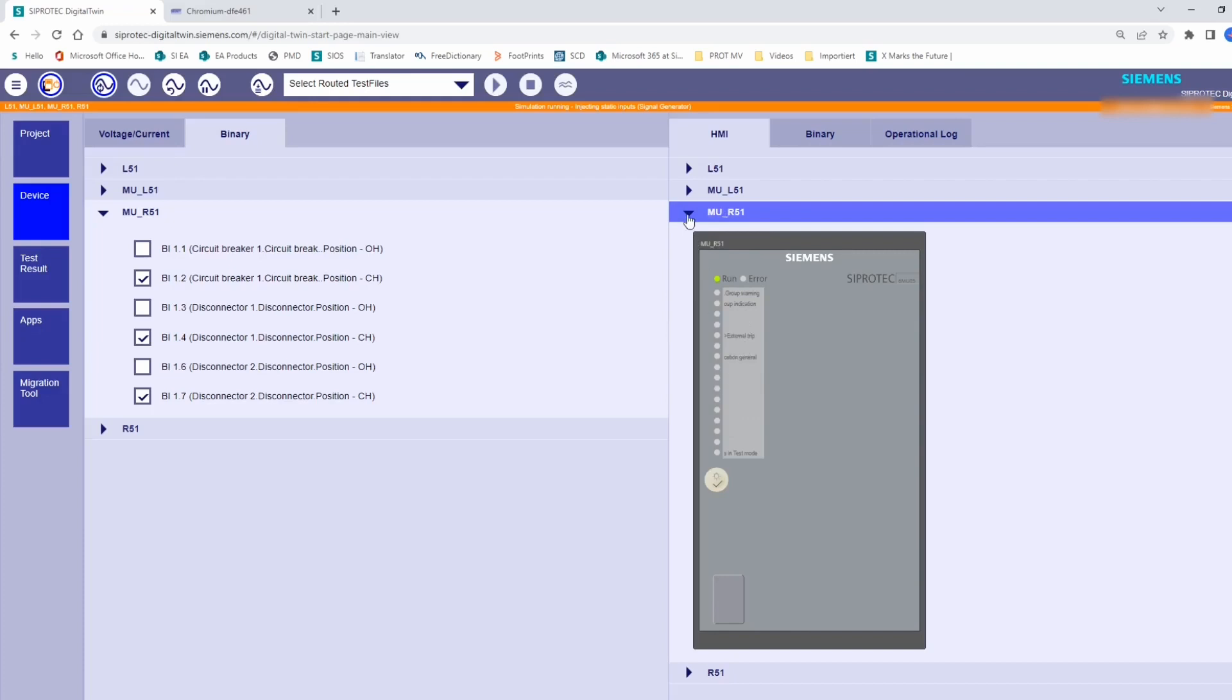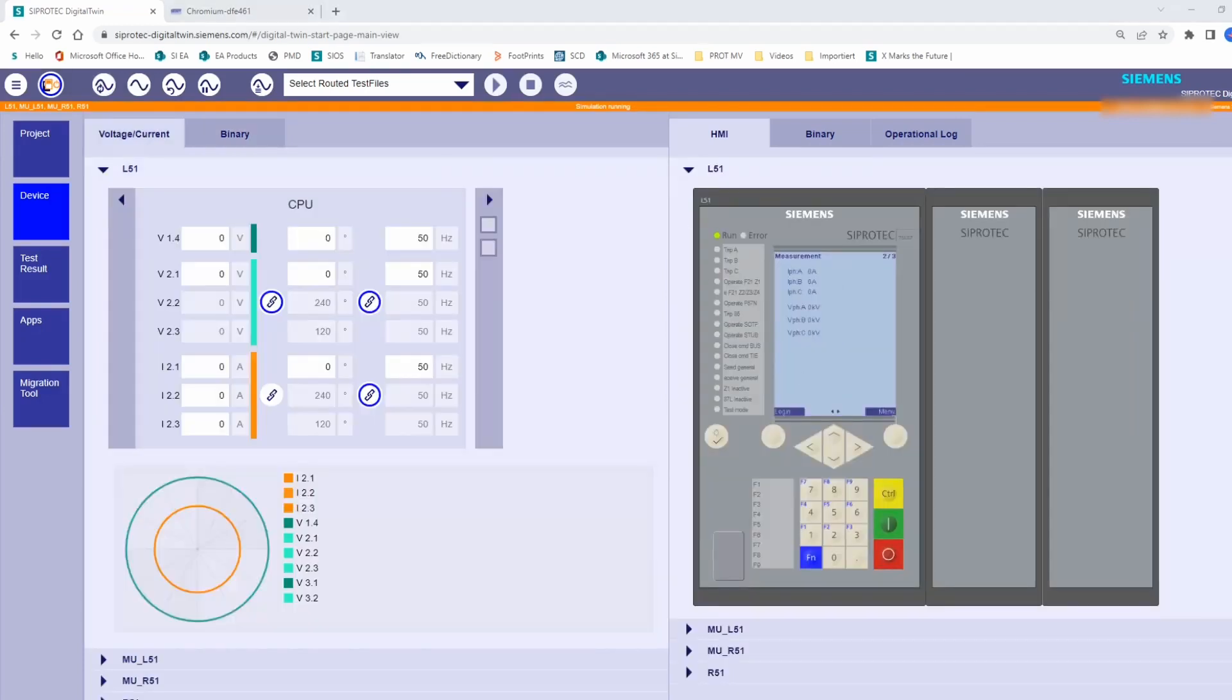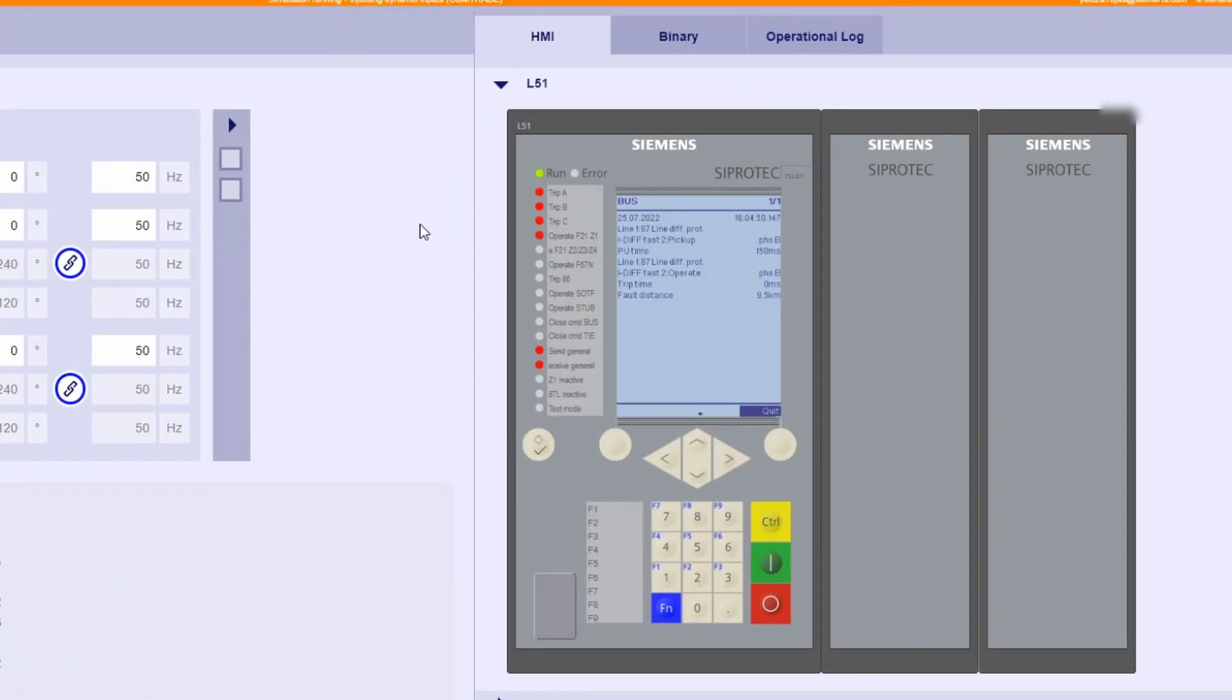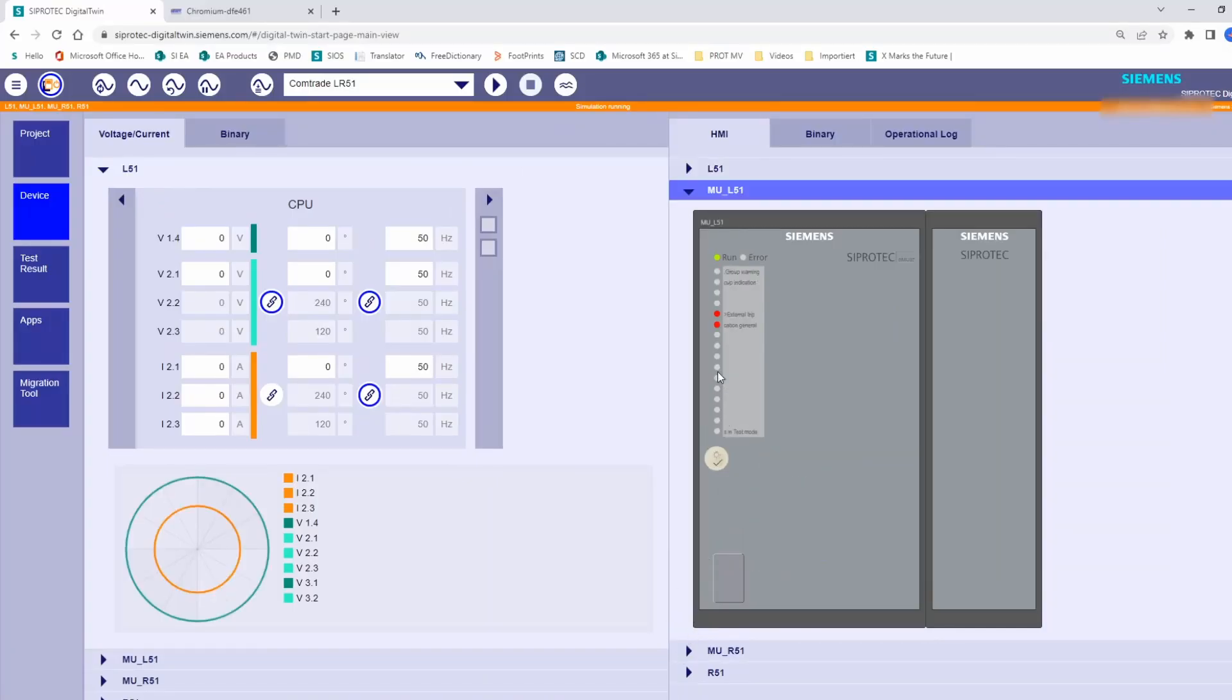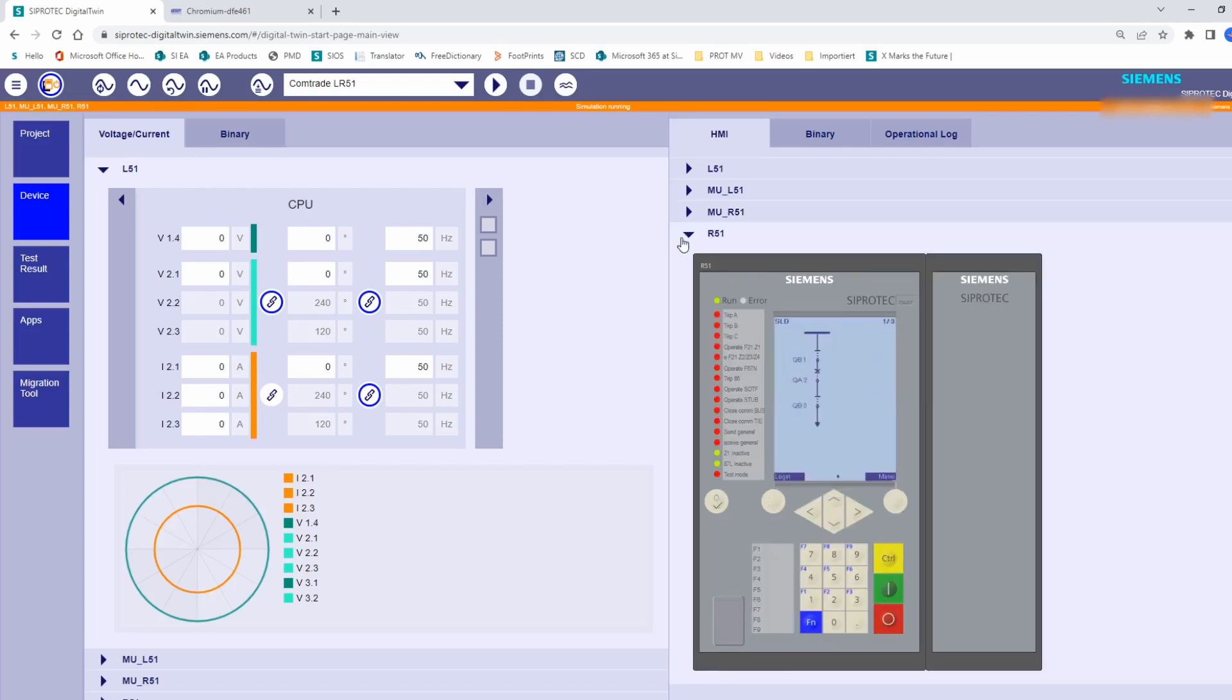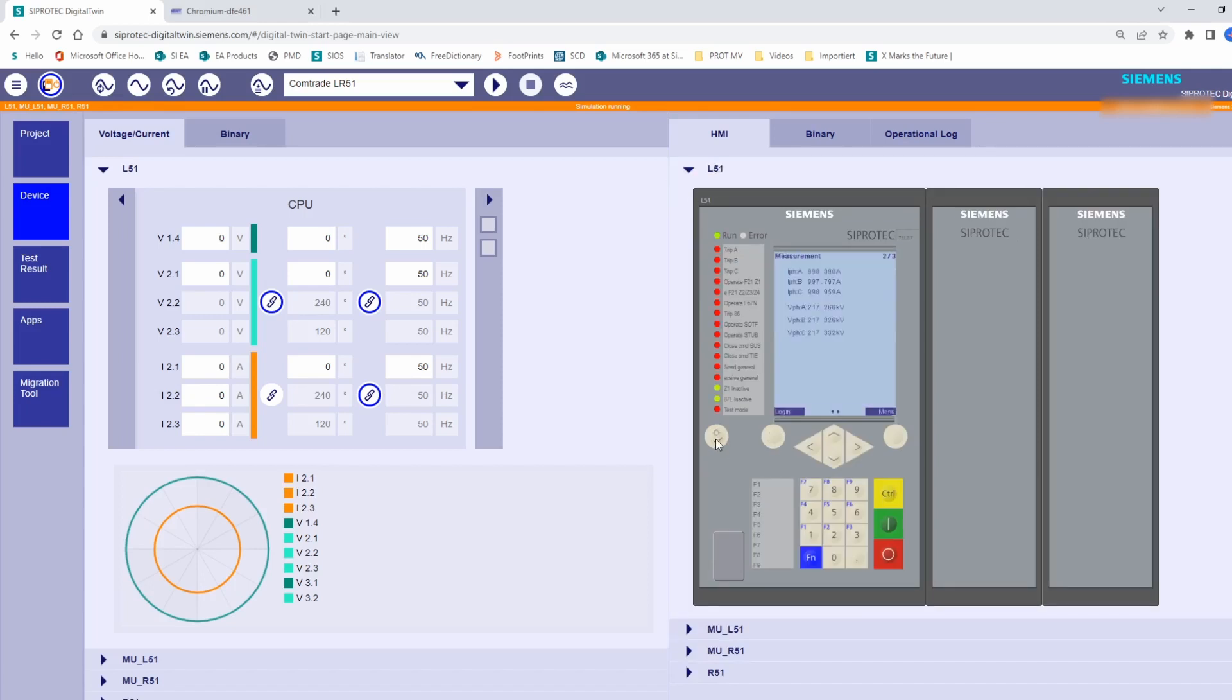Now we are ready to start with the protection functionality test. First, we want to test the line differential protection. Remember, we have already prepared the COMTRADE file, so now we are going to replay it and analyze the response of the protection devices. We select the COMTRADE and then we click on the play button. L51 has tripped by line differential protection due to a failure in phase B. In the MU-L51, the LEDs indicate that the trip has been received and processed by the merging unit. If we check the device located in the right side of the line, R51, we see that it has also tripped by phase B, and the MU-R51 has received and processed the trip as well. We clear the LEDs and displays on the devices and get prepared for the next injection.